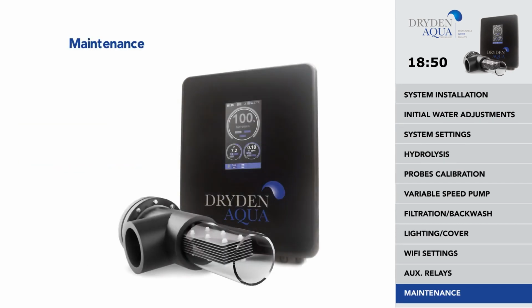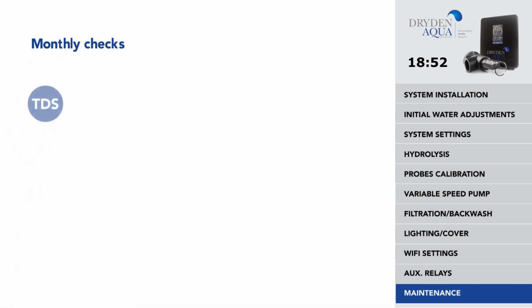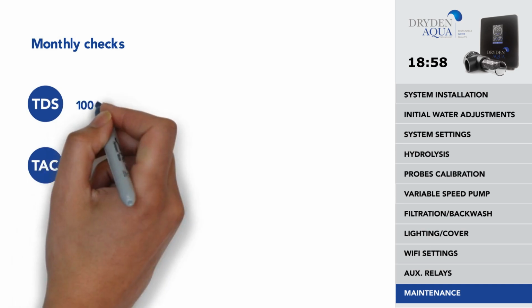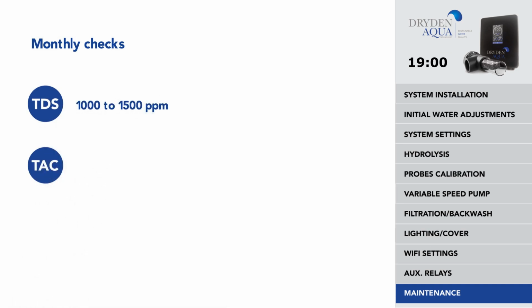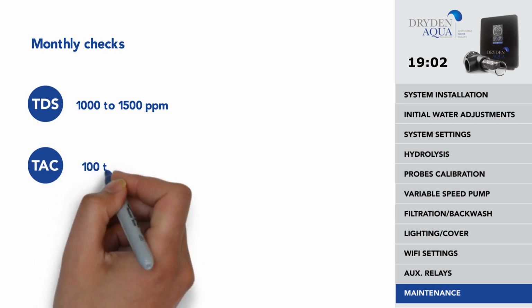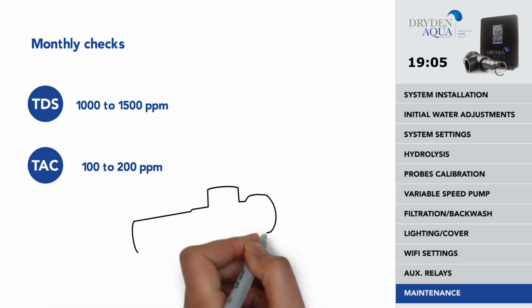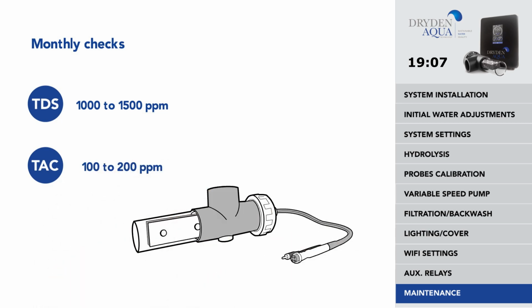Maintenance. Once a month, we recommend to check and correct TDS and alkalinity levels if necessary. Keep TDS level between 1000 and 1500 ppm and alkalinity between 100 and 200 ppm. Visually check the hydrolysis cell to detect incrustations. If necessary, clean the cell.